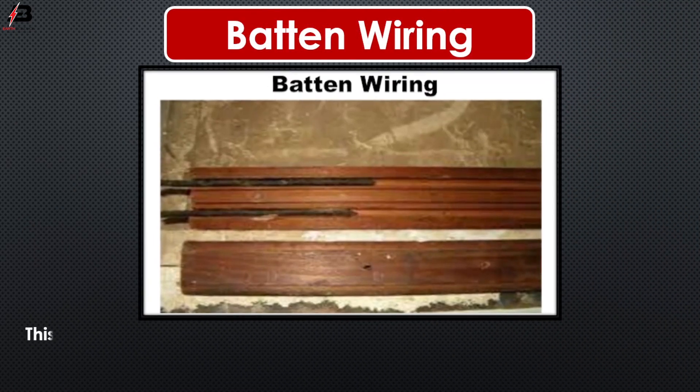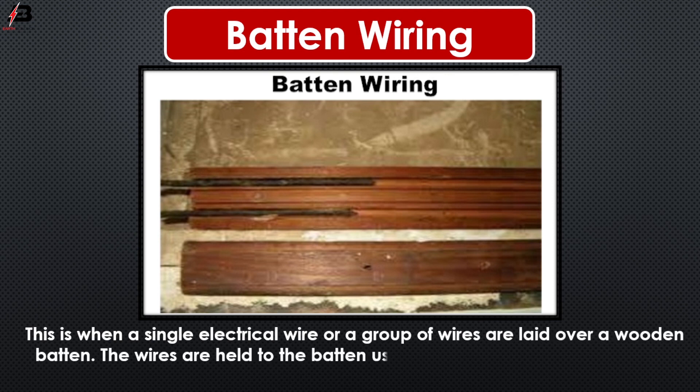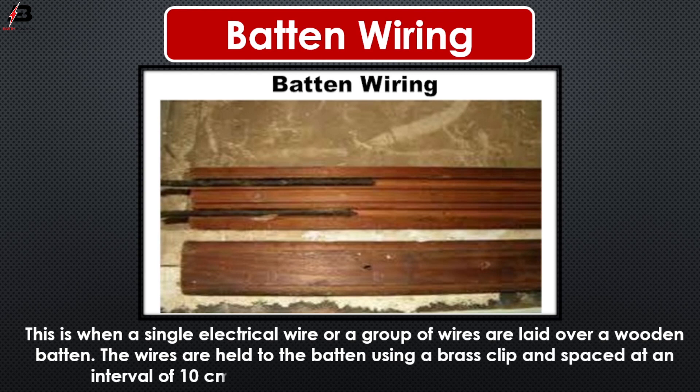So viewers, let's start. Batten wiring. This is when a single electrical wire or a group of wires are laid over a wooden batten. The wires are held to the batten using a brass clip and spaced at an interval of 10 cm for horizontal runs and 15 cm for vertical runs.